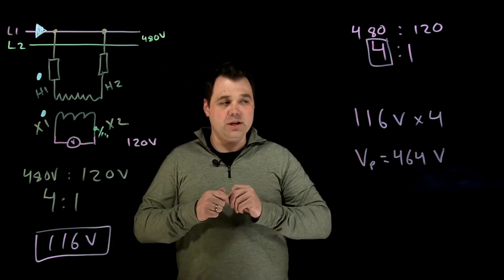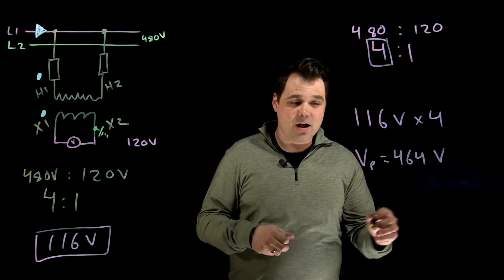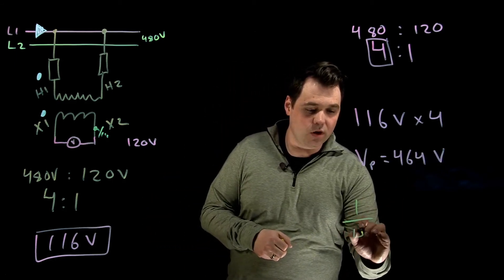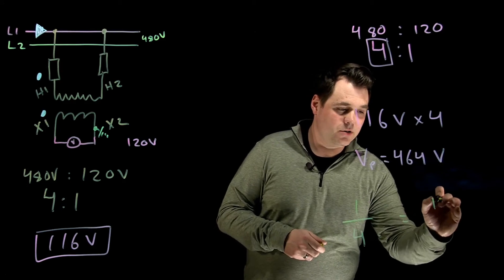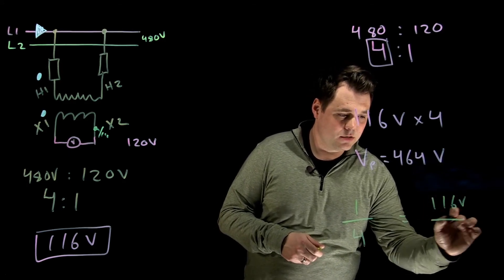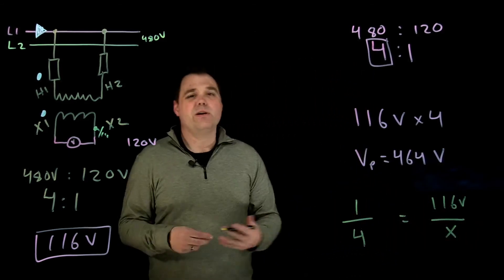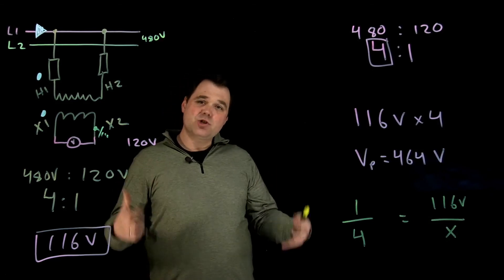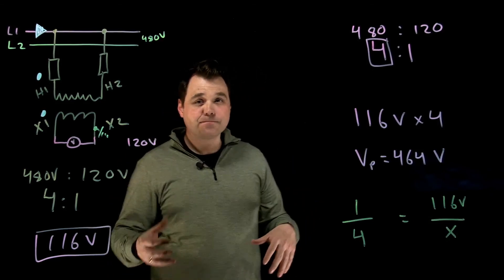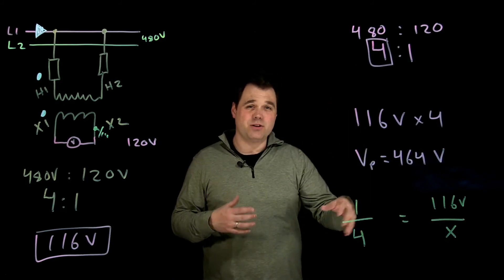This comes down to a little bit of a relationship. You can set it up by going 1 to 4 is equal to 116 volts over x, and rearrange that formula to calculate. That's kind of the general idea behind PTs and a basic calculation.